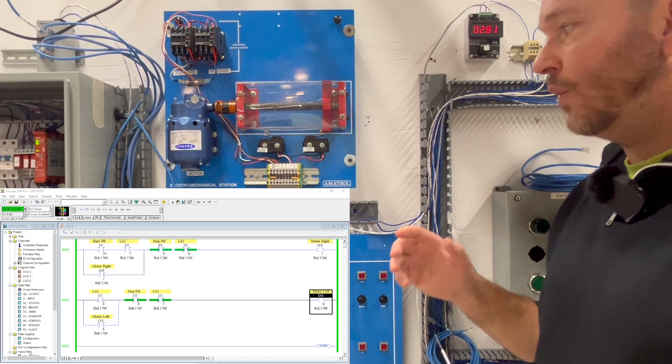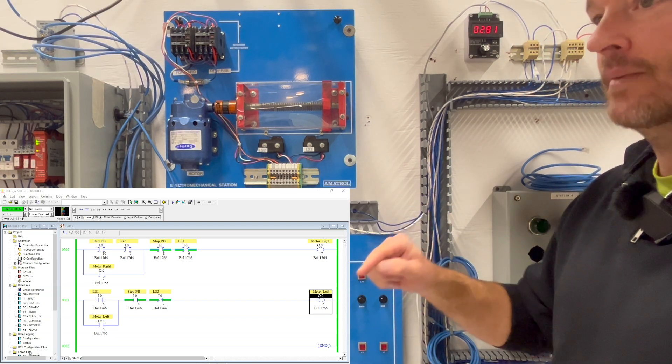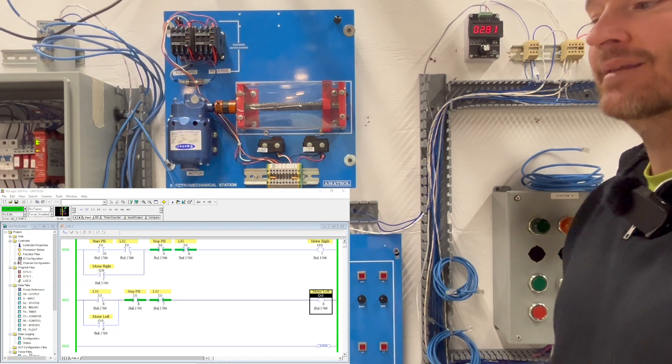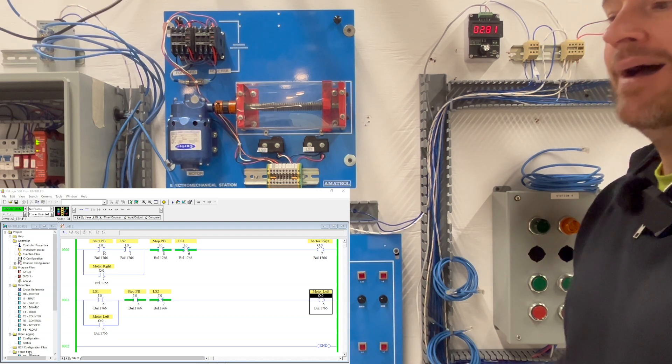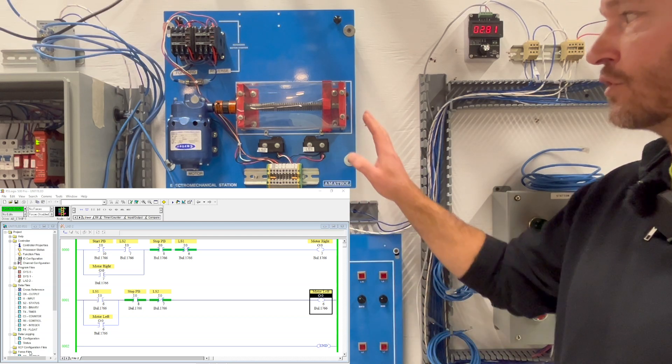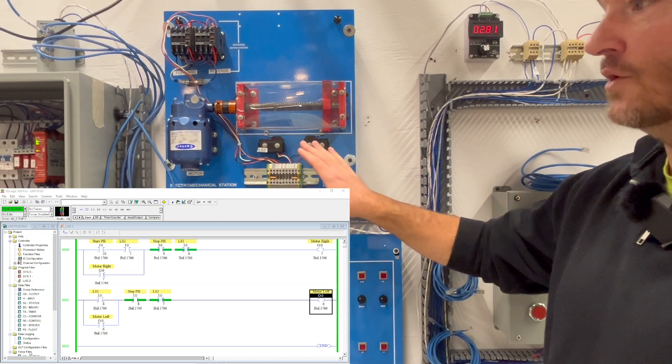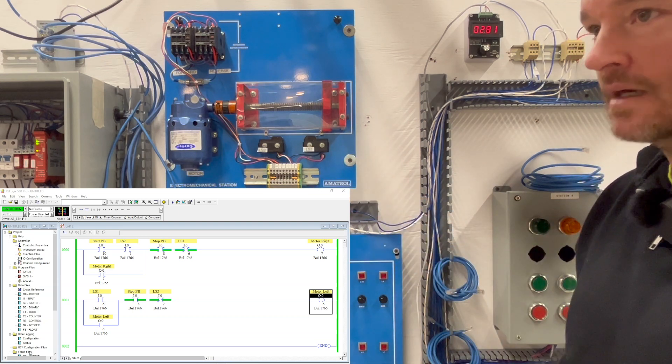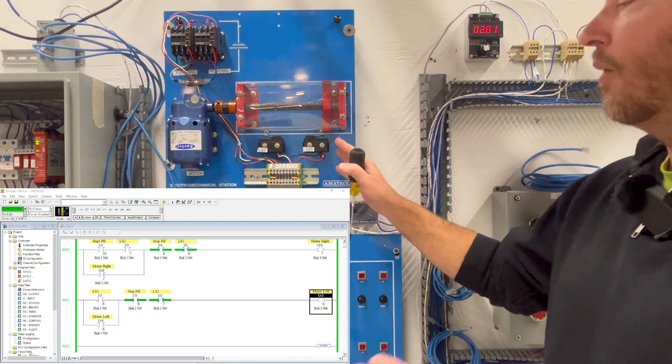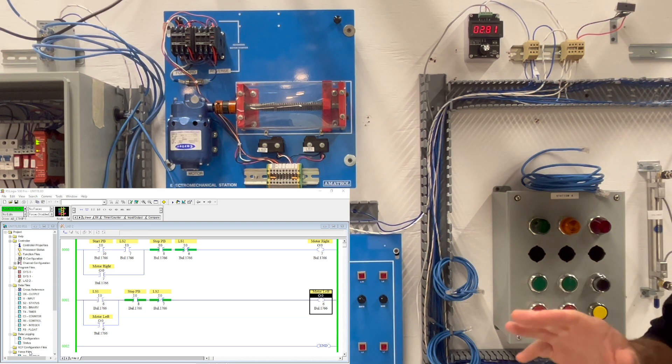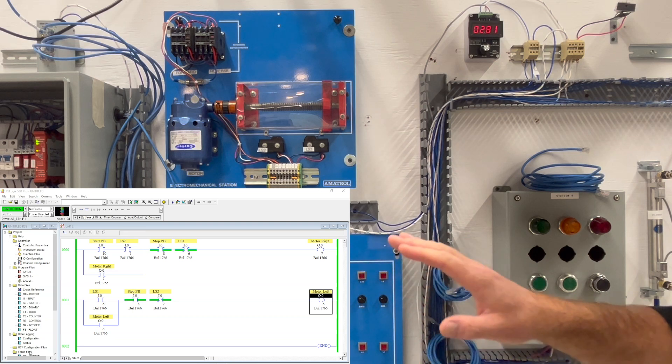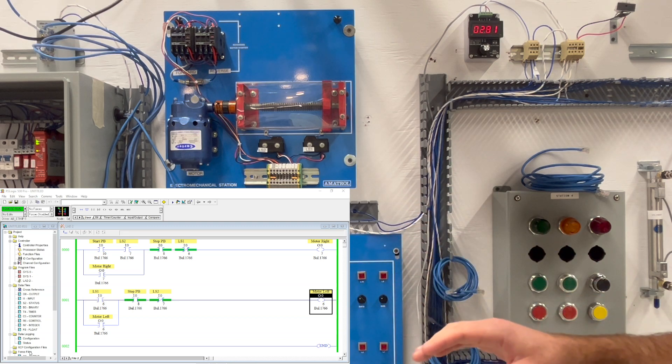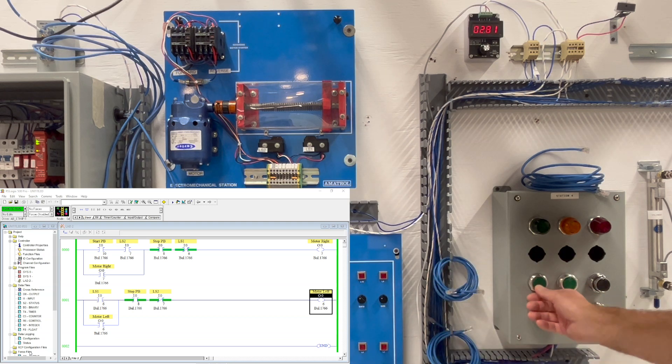Now when I go to troubleshoot this I know that the program has worked before, so unless something has changed in the program I'm pretty confident that there should be no issue here with the program. So I'm guessing it's some type of wiring or one of my inputs has gone bad. So while this is up I'm going to go ahead and I can watch this, I can activate these inputs to see what's going on.